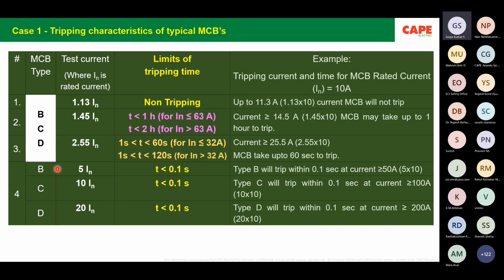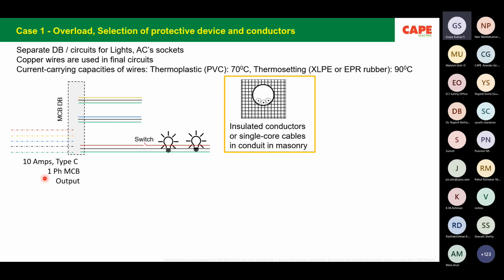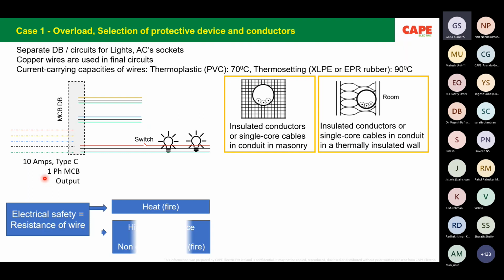In contrast, the actual situation in the field is that in some cities, or there are several cities in India, type B MCBs are not available to purchase over the counter. As a result, building owners go for type C. If you look at the characteristics of type C, the instantaneous tripping current is a little bit higher, or double, than type B MCB, which means we are going into a somewhat dangerous situation. So selection of MCB is very much important. What I have seen is Kerala is probably the only state in India where type B MCB is still used for wiring in houses. In most of the other states, type B MCB is very rare in the market, and the sellers always sell type C MCB, which is actually not correct. Probably this is also one of the reasons the number of accidents is a little bit lesser in Kerala in comparison to other states. The wires.